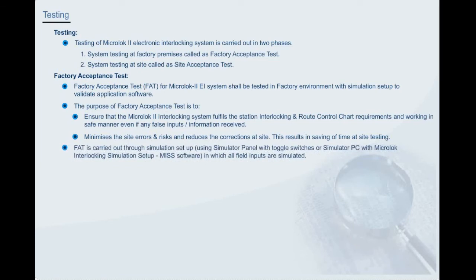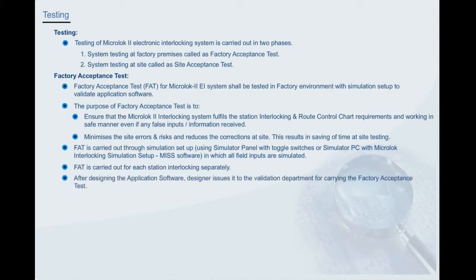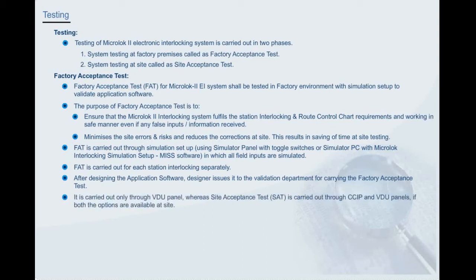Factory acceptance test is carried out through simulation setup using simulator panel with toggle switches or simulator PC with Microlok interlocking simulation setup MISS software in which all field inputs are simulated. Factory acceptance test is carried out for each station interlocking separately. After designing the application software, designer issues it to the validation department for carrying the factory acceptance test. It is carried out only through visual display unit, whereas site acceptance test is carried out through control indication panel and visual display unit if both the options are available at site.